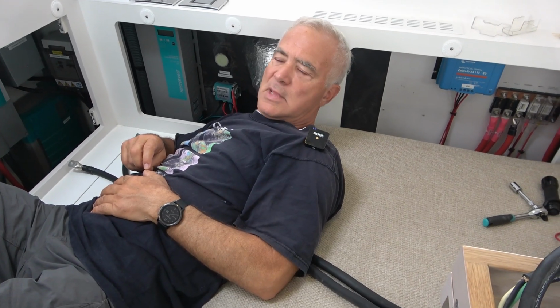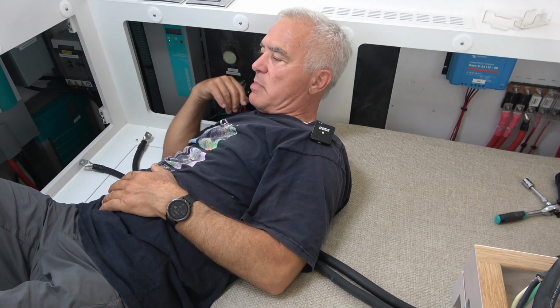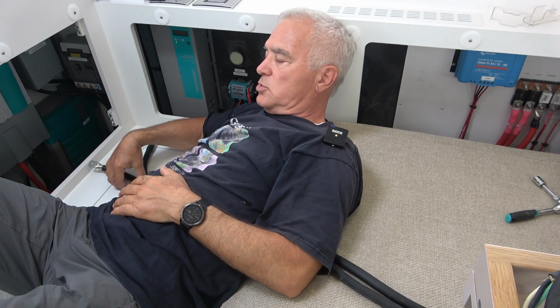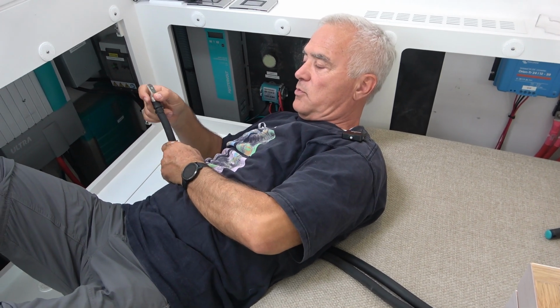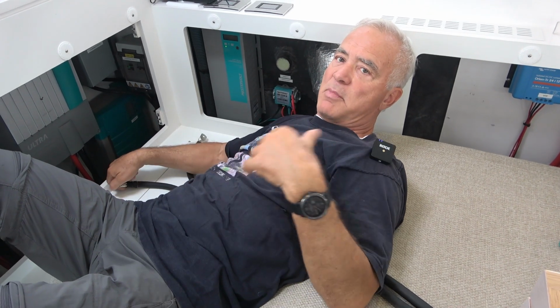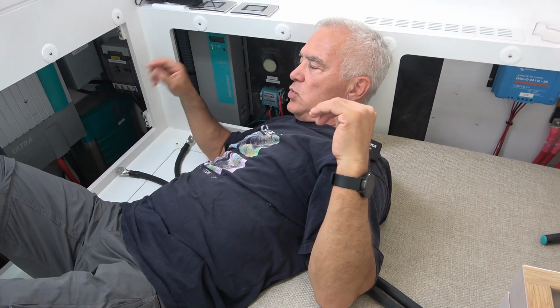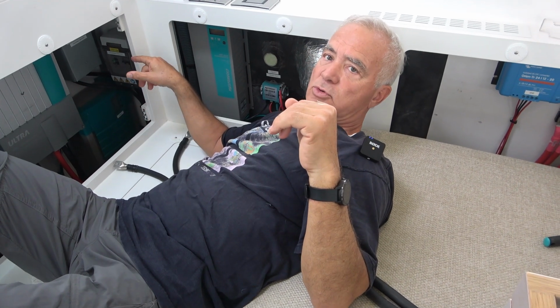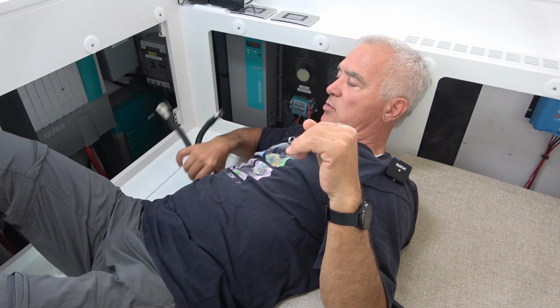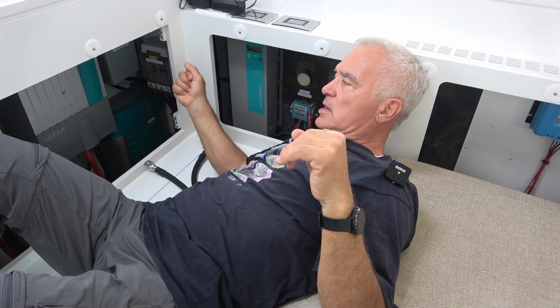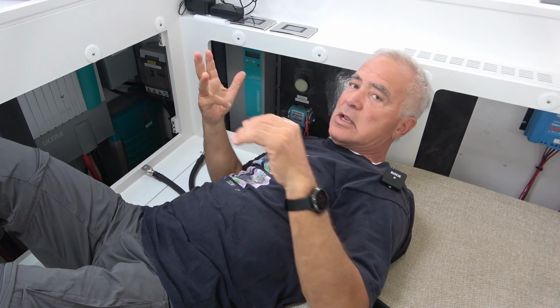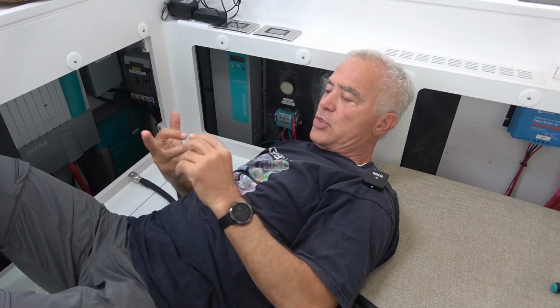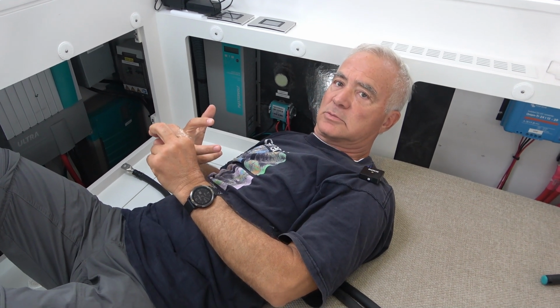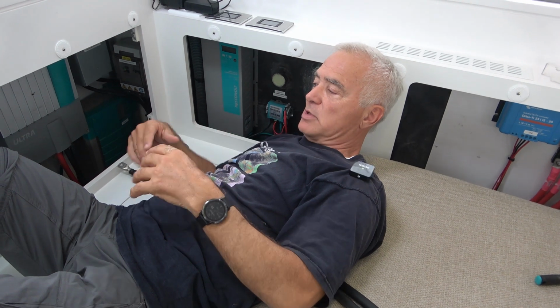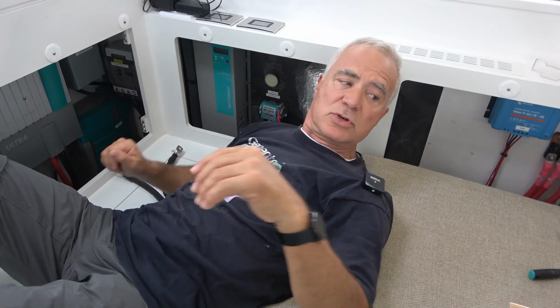So what do you have to do? Well, I have the 25 volts of the battery going into the charger. These are the big 95 millimeter cables going from the battery distribution bar to each one of those inverters, so I just have to add one set, which I have here. Then there is a second input, which is the shore power, and a third input, which is the generator power. Of course there are smaller wires, but still carrying 50 amps continuous requires a good gauge, which is this size.